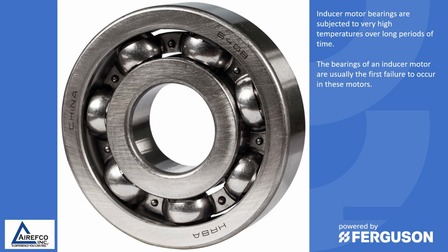When doing regular maintenance on a gas furnace, the bearings of the inducer motor need to be checked. Inducer motor bearings are subjected to very high temperatures over long periods of time. The bearings of an inducer motor are usually the first failure to occur in these motors.